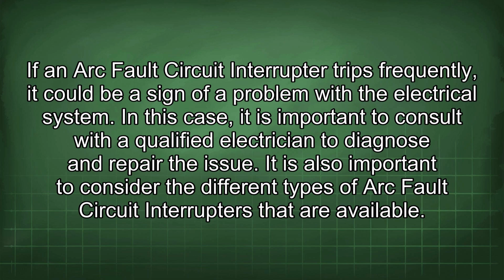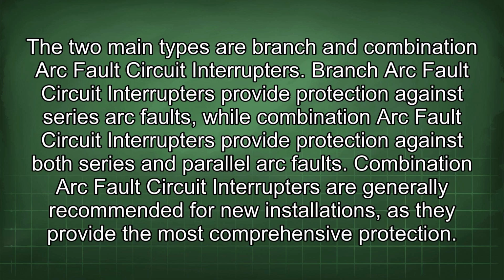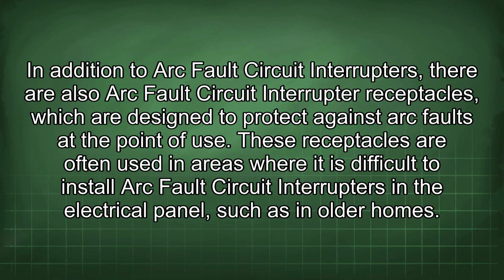It is also important to consider the different types of arc fault circuit interrupters that are available. The two main types are branch and combination arc fault circuit interrupters. Branch arc fault circuit interrupters provide protection against series arc faults, while combination arc fault circuit interrupters provide protection against both series and parallel arc faults. Combination arc fault circuit interrupters are generally recommended for new installations, as they provide the most comprehensive protection. In addition to arc fault circuit interrupters, there are also arc fault circuit interrupter receptacles, which are designed to protect against arc faults at the point of use.